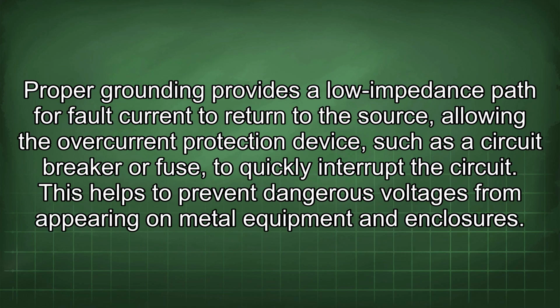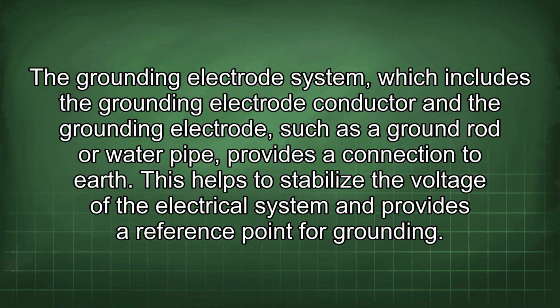Proper grounding provides a low impedance path for fault current to return to the source, allowing the overcurrent protection device, such as a circuit breaker or fuse, to quickly interrupt the circuit. This helps to prevent dangerous voltages from appearing on metal equipment and enclosures. The grounding electrode system, which includes the grounding electrode conductor and the grounding electrode, such as a ground rod or water pipe, provides a connection to earth.